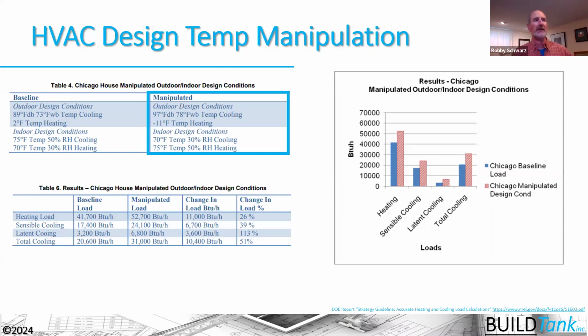So outdoor design conditions were manipulated, and they saw ultimately that it changed the loads pretty dramatically. The heating load was changed 26%, sensible cooling by 39%, latent cooling by 113%, and total cooling by 51% here. So really, we want to look at the heating load and the total cooling there. You can see that if those design temperatures are manipulated and not entered properly, we're not going to get the right loads in our HVAC calculations. And we'll see how these things are impacted in other ways as well.